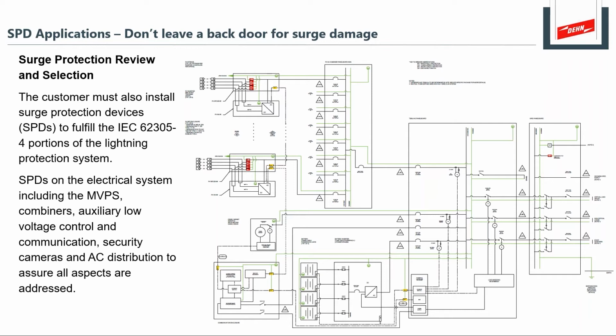Solar power generation facilities have their set of challenges. Combined cycle generation also has a very high degree of challenges. And so what we can do is look at the entire power plant distribution, the low voltage and medium voltage distribution systems, and we can use that to apply proper surge protection measures. And what we learned from things like Hurricane Sandy and the Fukushima disasters is that the backup generator systems are extremely important at a power generation facility. So the backup generation, the transfer switch associated with that backup generator, these are all extremely important aspects at a power generation plant that we need to make sure have proper surge protection measures installed.